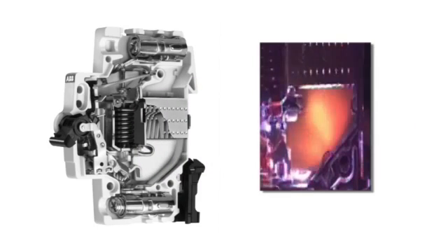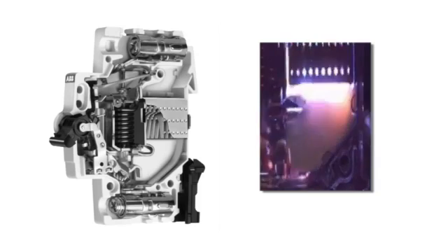The following is actual high-speed footage of an ABB miniature circuit breaker clearing a downstream fault. In real time, this entire event takes place in less than 3 milliseconds. Within a half millisecond after the short circuit current is released, the coil registers the increased current due to the fault. The hammer trip forces the contacts to open while current continues to flow through the arc, which still exists between the fixed and movable contacts.